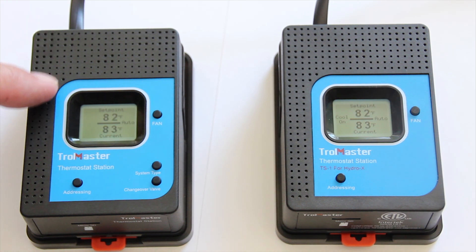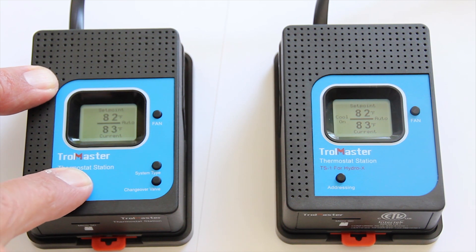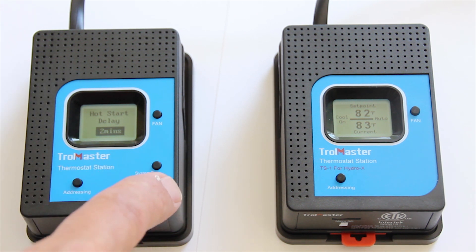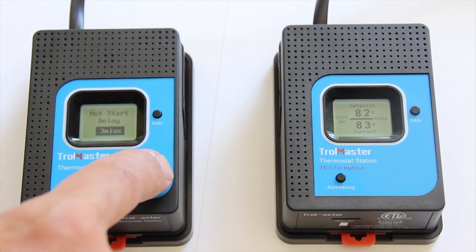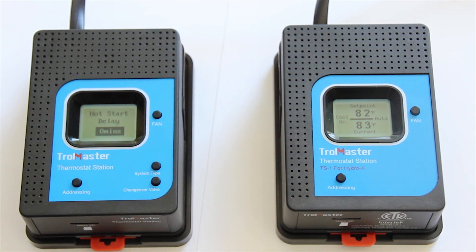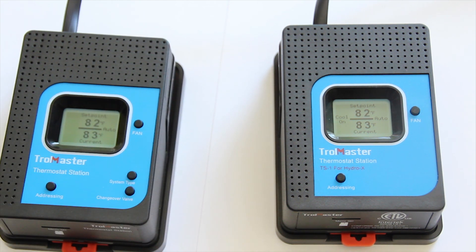From TrolMaster, going over the latest firmware update for the TS2 and TS1 — it does allow you to remove the hot start delay. After you do the firmware update, simply press and hold the addressing button for five seconds. It will pull up the hot start delay time, and you can use these two buttons right here to alter that, so you can go from five minutes to zero minutes. Then press and hold the addressing button for another five seconds to go back to the main screen.